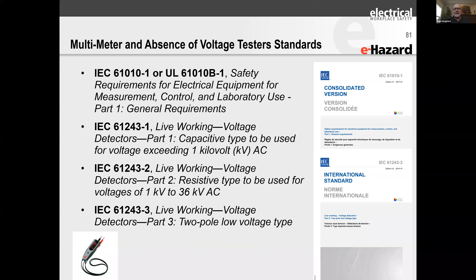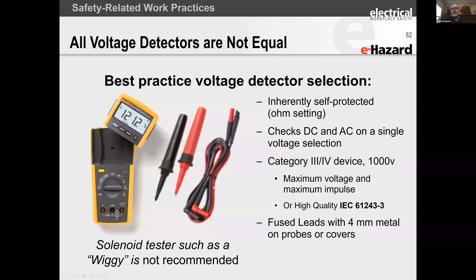And then if you use a multimeter, you're going to use the IEC 61010-1, and that's our UL equivalent, exactly the same standard that UL has an MOU on. And we recommend you use those. But if they're properly built and meet that standard, they won't take 5,000 volts, because they have to be really accurate for low meter use. We recommend using an IEC 61243-3 for absence of voltage verification because it's just a safer device if you get it on a higher level. They're not all created equal. Get high quality tools. Make sure you're following the right standards. 61243-3, this one meets 61010.